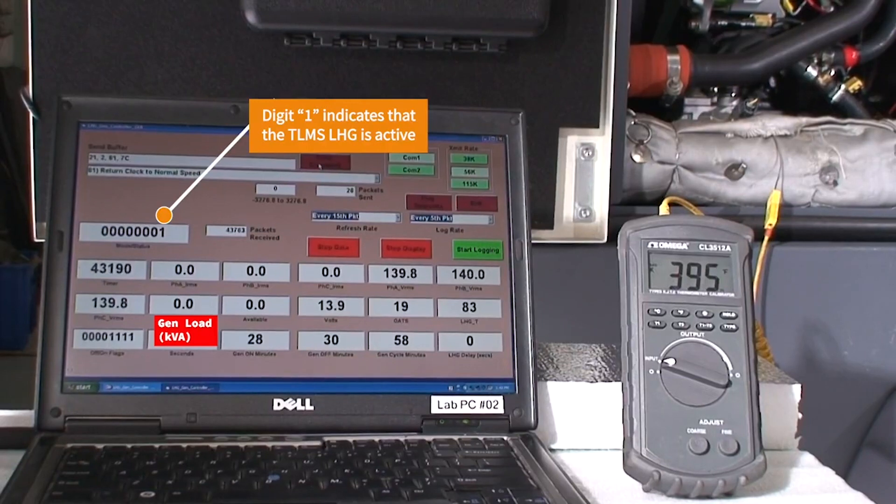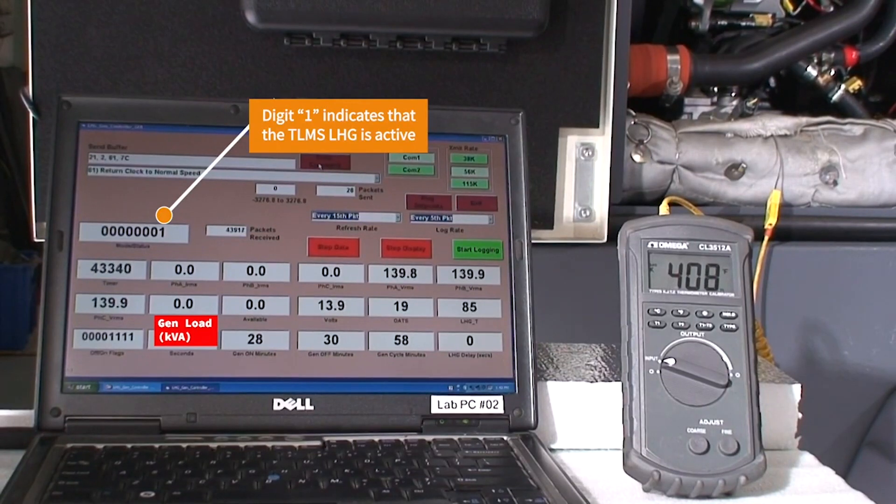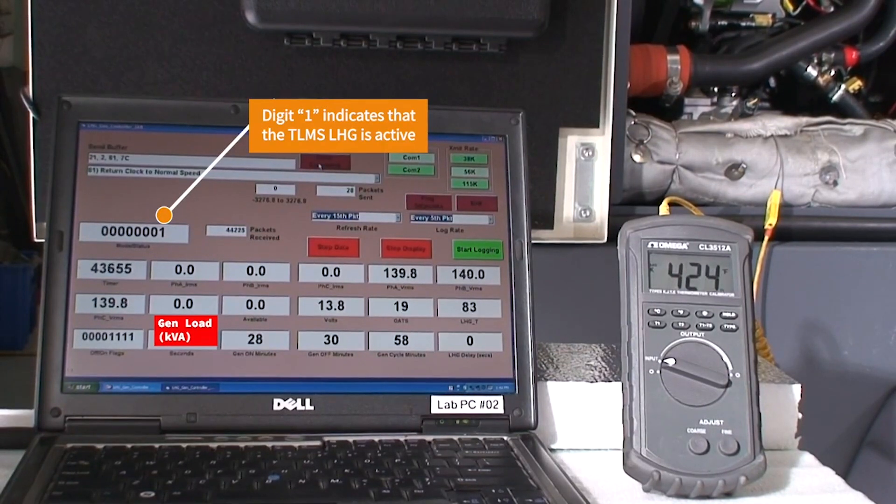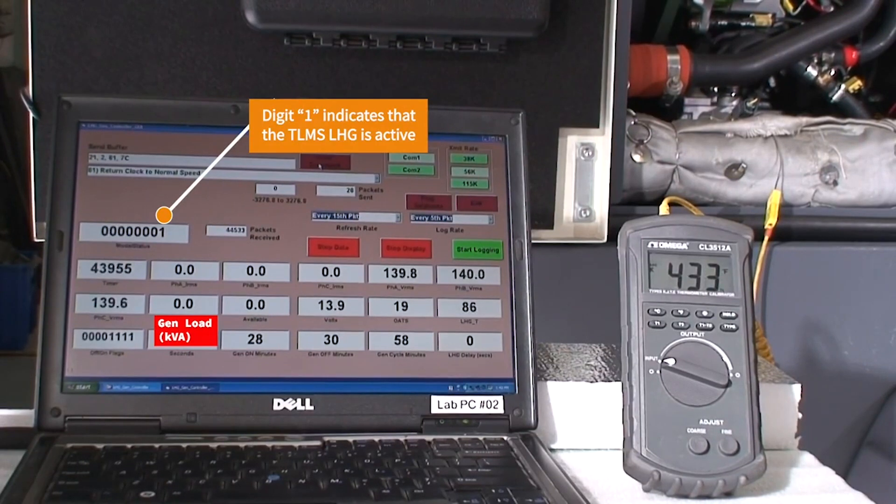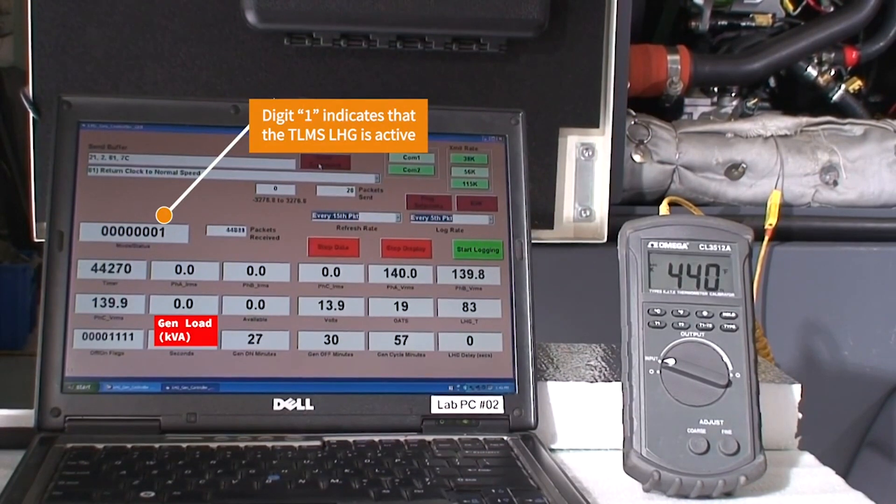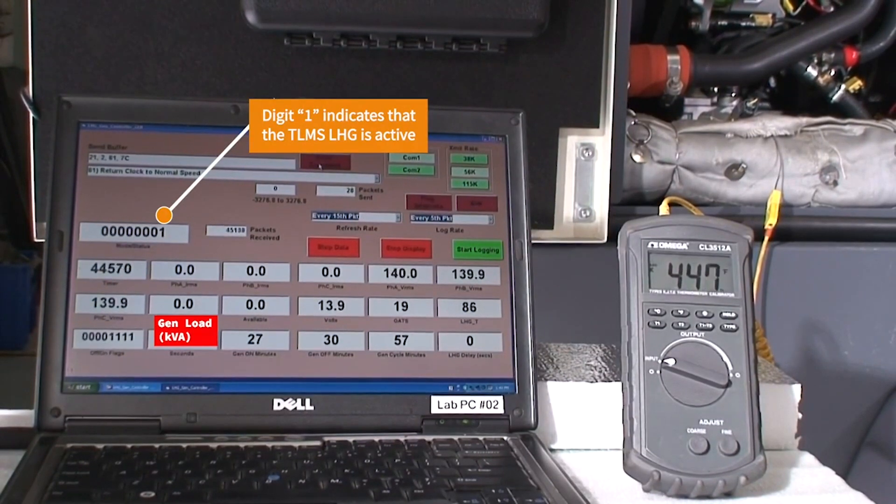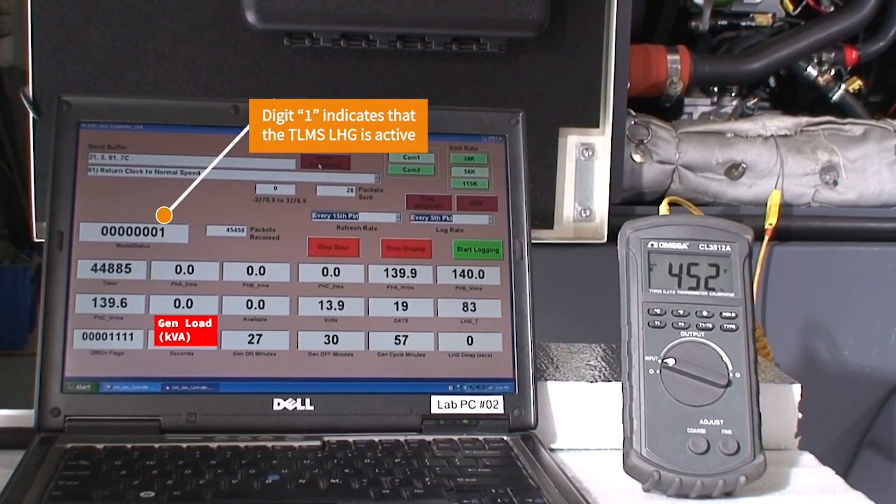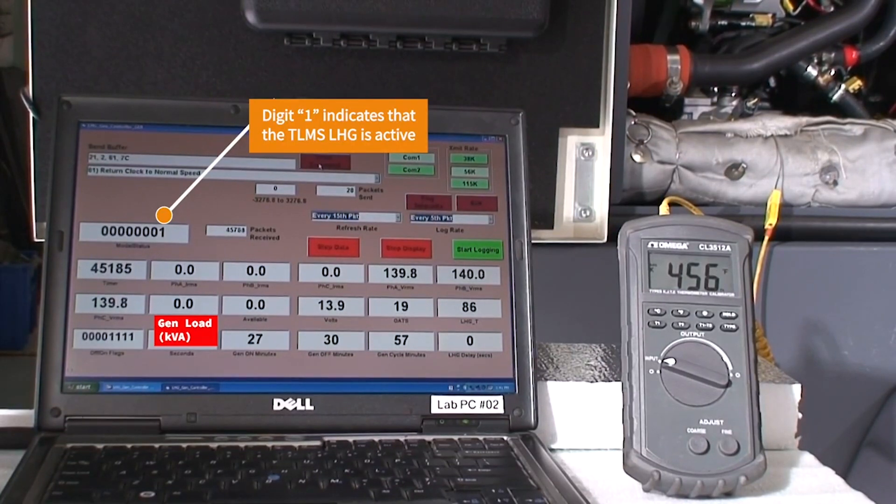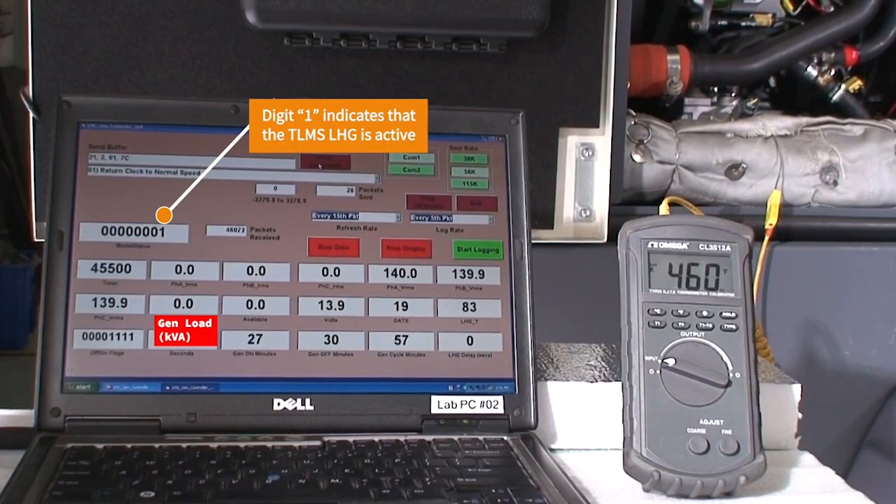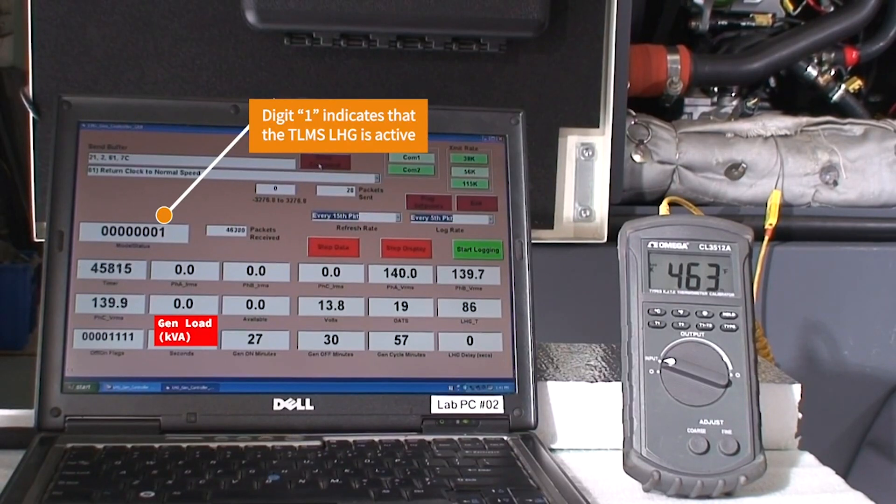The LHG is applying about 10 kilowatts of load to the engine and this is causing the exhaust gas temperature to rapidly rise to about 495 degrees Fahrenheit. All the energy that is being converted by the LHG is being directed as heat in the coolant and being steered back into the engine.